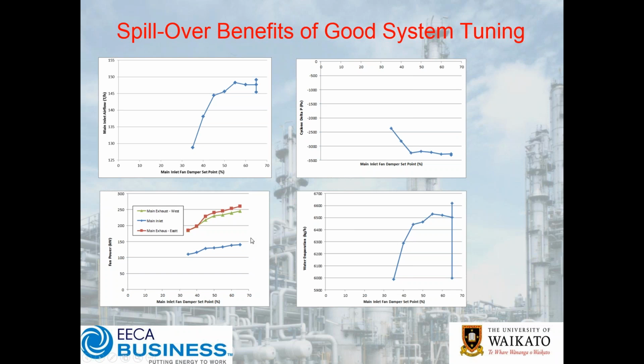And what you can see is the energy drawn by the plant was quite dramatic as we come back down here. So there's about 140 kilowatts of savings coming from here to there with the same production. Now in the middle actually there's a bit of a production increase. What you need to be mindful of is superimposed over this we've got some other metrics.